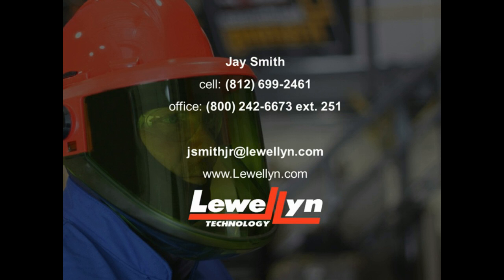At what point does the Arc Flash PPE category method make sense to use? The category method makes sense in a service type of industry. If you're going in to service equipment and you don't have the luxury of seeing an Arc Flash label, you can't just refuse to do the job because the client didn't do an Arc Flash study.